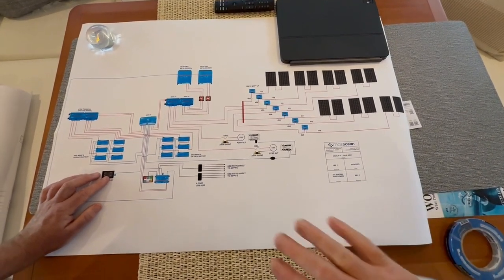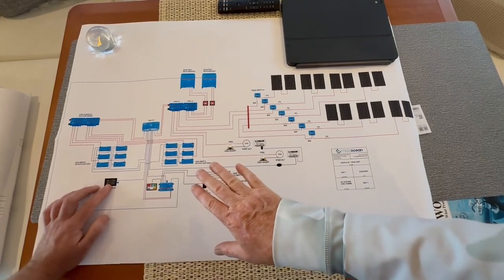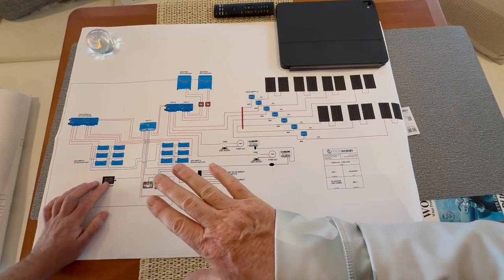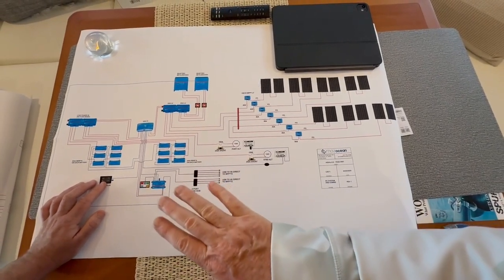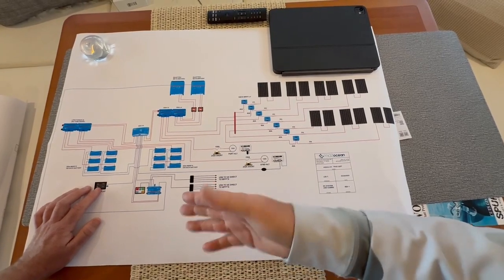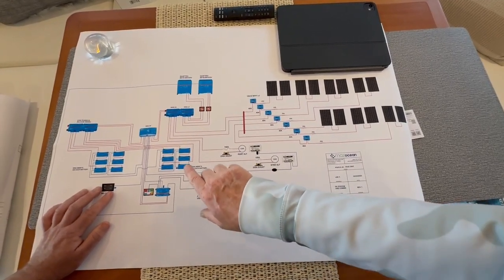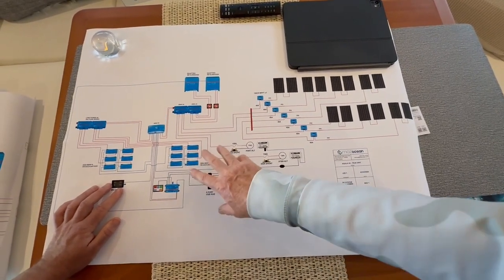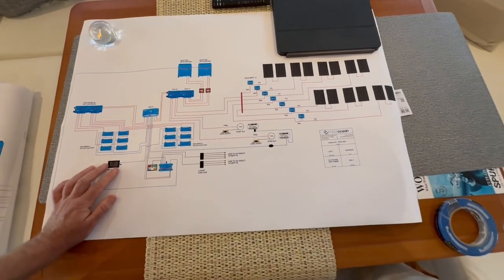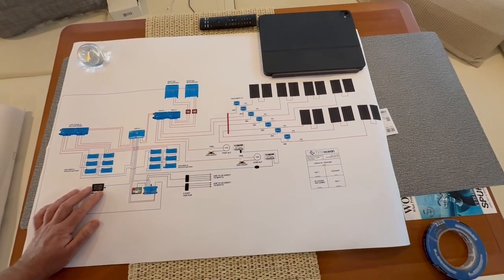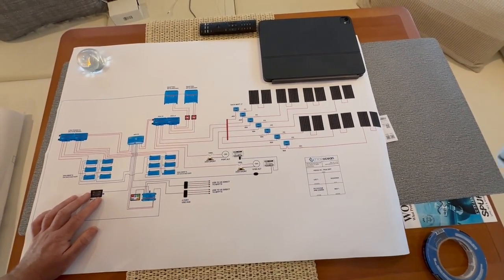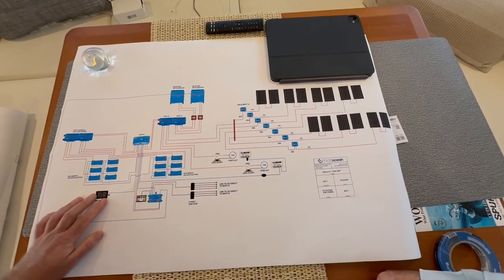Now there was an important part when we made the conscious decision to do this, about the wiring and voltage drop. We were very careful to make sure we matched the lengths of the cabling so they were as close to the same, or mirrored, as possible, to maintain the balance of the batteries.